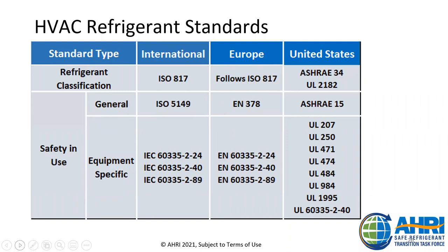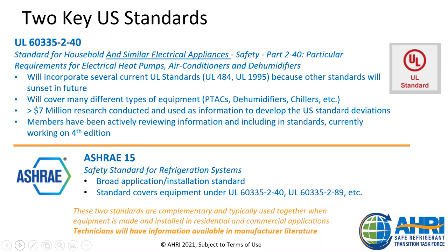So specifically, there are two very important standards for the HVAC or AC and heat pump systems in the US. The UL 60335 2-40, which I call the UL 2-40, is a standard for household and similar electrical appliances. And the ASHRAE standard 15 is the safety standard for refrigeration systems. The UL 2-40 includes product design requirements specific to electromechanical safety. And ASHRAE 15 determines requirements for safe installation of those products. So the UL 2-40 covers many different types of equipment used in human comfort, cooling, and heating, and it is replacing a previously used safety standard, which is, I guess, much more popular, the UL 1995. And we are currently working towards the fourth edition of the UL 2-40 standard.